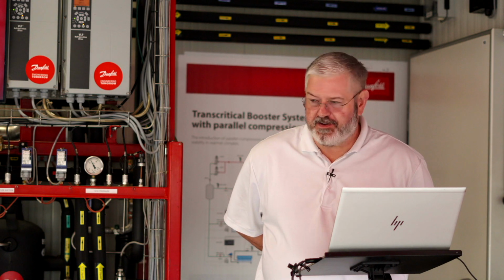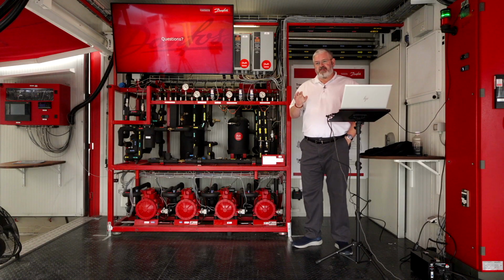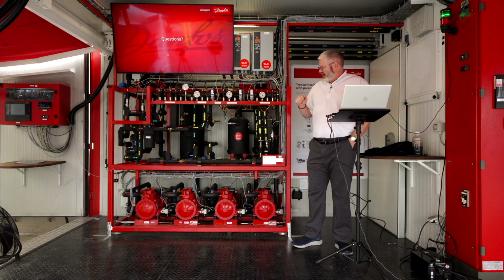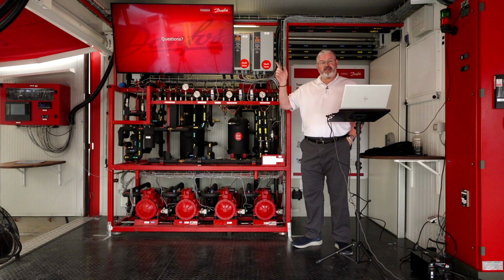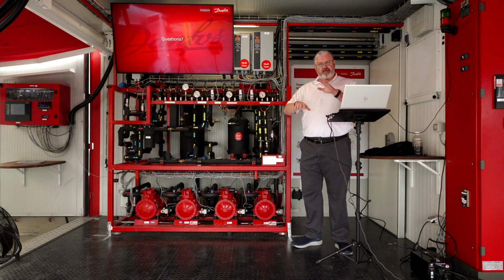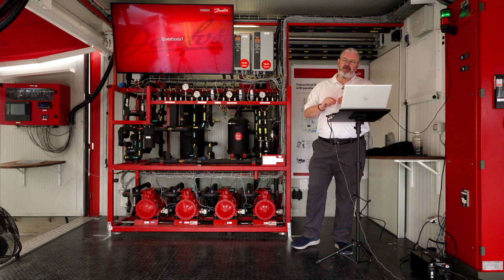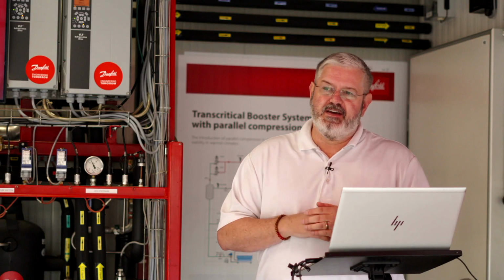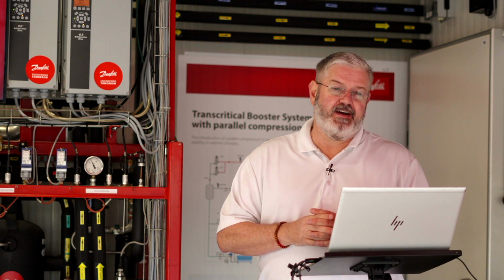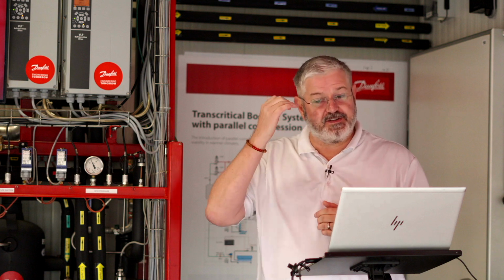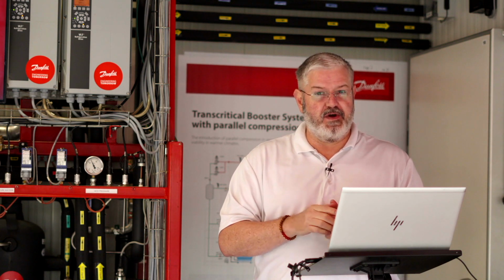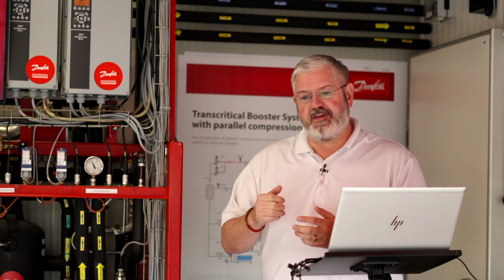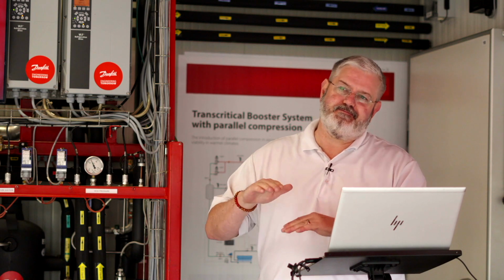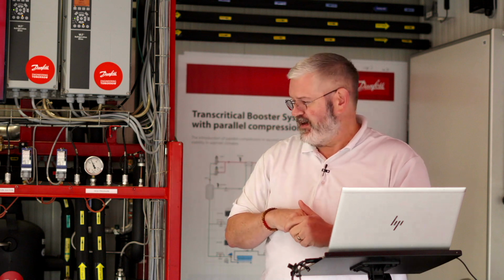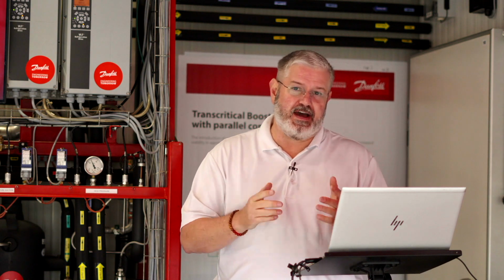A question is, what are the symptoms of low refrigerant level and how is refrigerant level monitored? That's a great question. Most of the manufacturers will put both a high level switch and a low level switch because both conditions are bad. If you hit the high level switch, you've got too much liquid in the system. You may have some variance in the system based on having reclaimed devices like that. The low level switch is important because if you're not sending liquid to the evaporators, you're not removing heat. The symptom would be that you're struggling with cases making temperature. You don't have enough liquid in the system, you can't pull everything down, so you would see temperatures rising. You should have gotten an alarm for that, by the way, based off the low level switch. And if you'll remember from earlier, we just charged the flash tank to above the bottom sight glass, and that puts you maybe 10 or 15% up the flash tank away from the low level switch. But yeah, if you went completely dry, you're just going to stop cooling and have high temperature alarms.